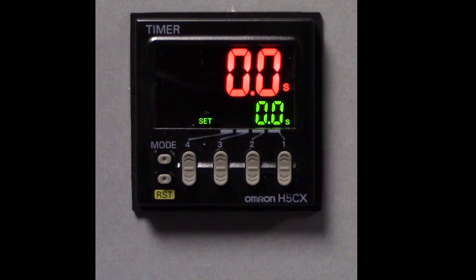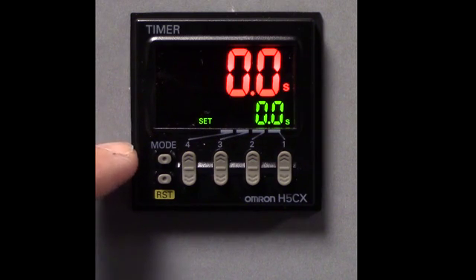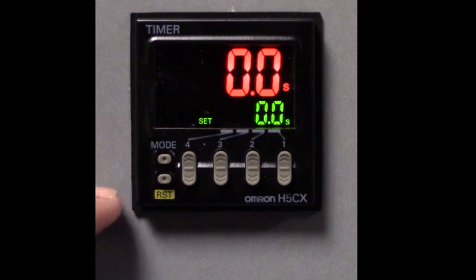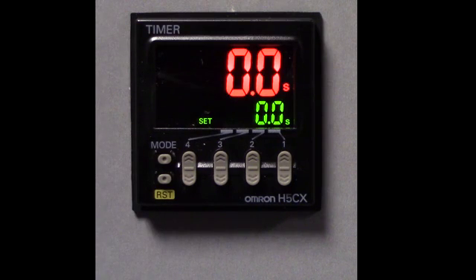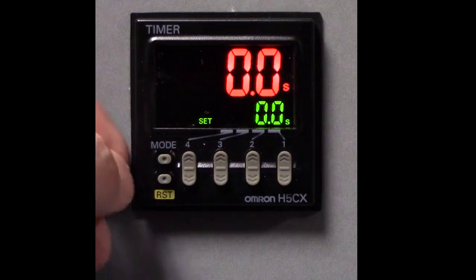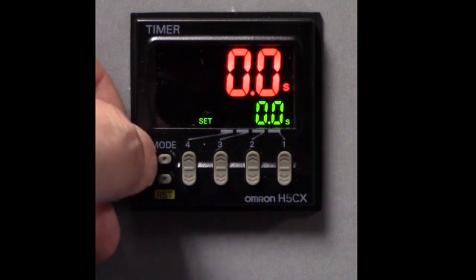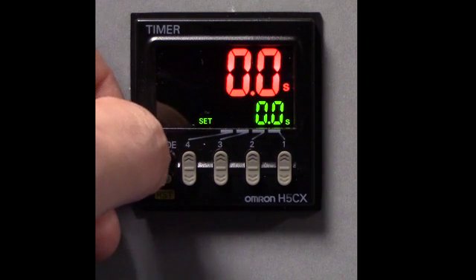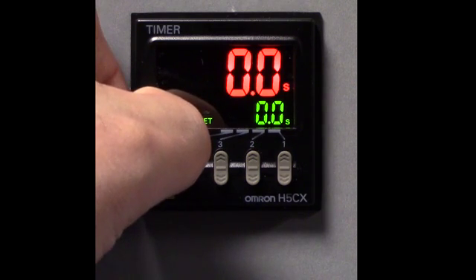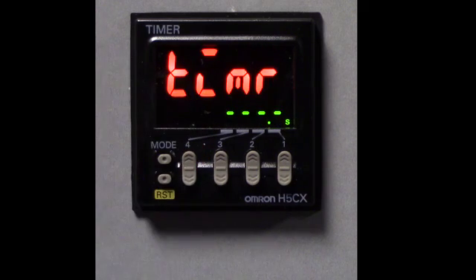What I'd like to call to your attention on the left-hand side of the timer are two buttons. The first one is called the mode key, and the second is called the reset key. The mode key allows us to advance through the various functions of the timer when programming it, and the reset key allows us to reset the timer when it reaches its end result in the timing sequence. So right now I'm going to press the mode key, hold it for 3 seconds, and that'll get us into our first function of the timer. The first function of the timer is setting up the timing sequence.